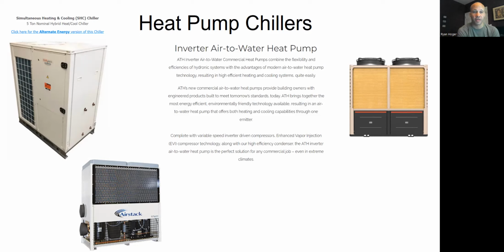The one in the upper left there, that particular brand, at my office, we've been using that for 12 years. It gives you an idea of how long some of this stuff has been around. That manufacturer used to just make chillers. And then one day somebody asked about heating, and they just decided to make a reversing valve in there. It's literally that simple. I mean, obviously there's more than that, but conceptually you're just adding a reversing valve, just like we did on the regular, small residential heat pumps. Just add a reversing valve, and all of a sudden this thing can flip modes and swap its evaporator and its condenser's jobs. So that's what this thing does as well.